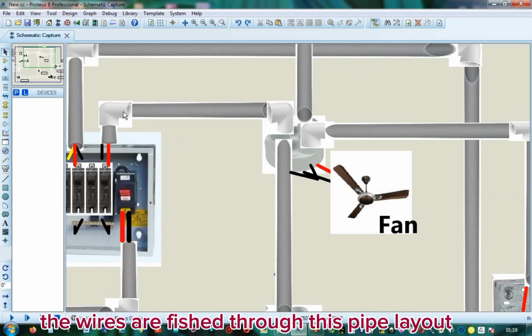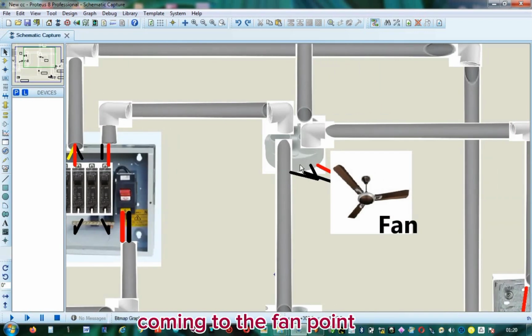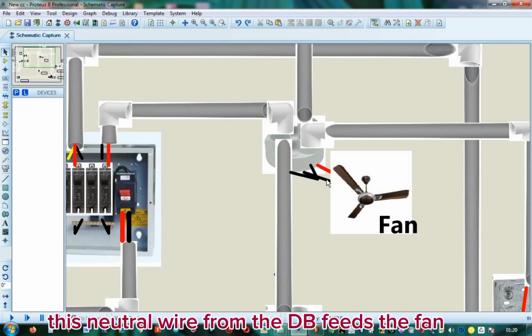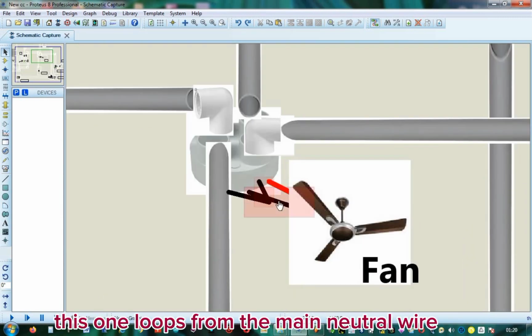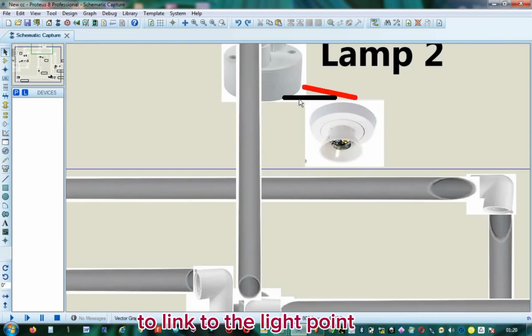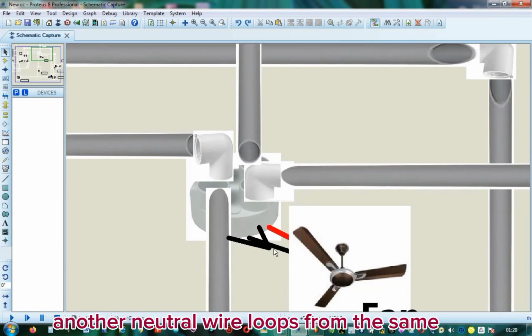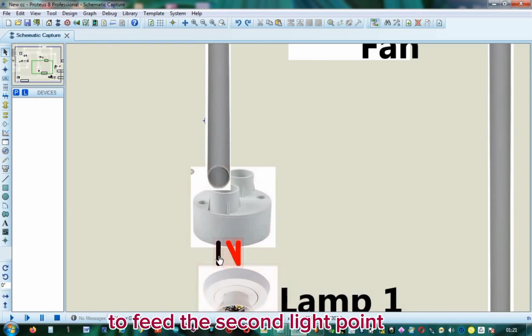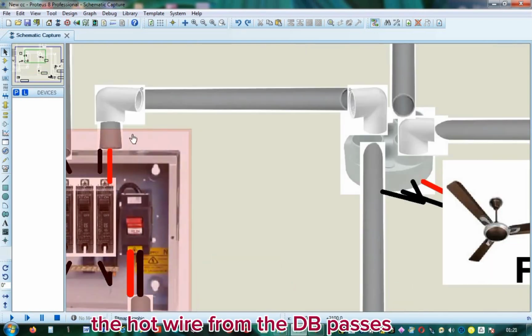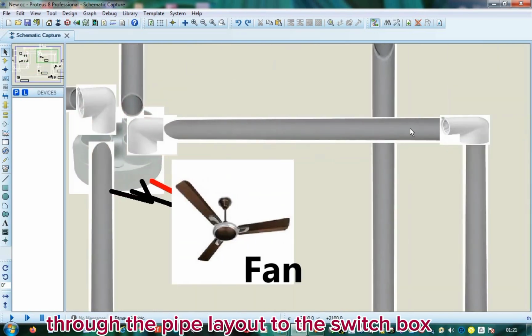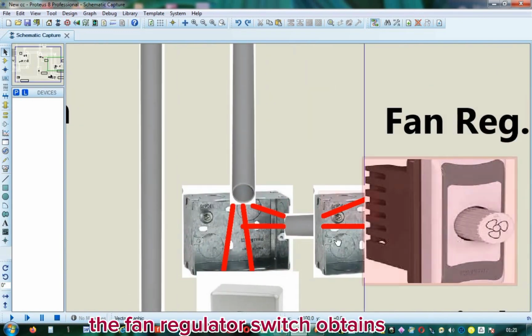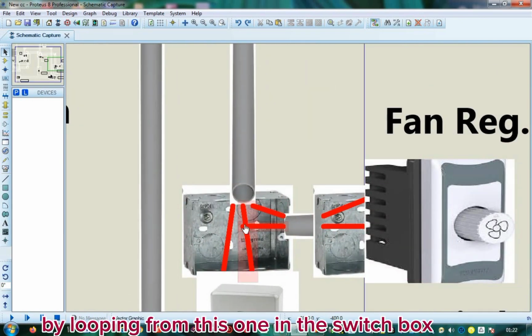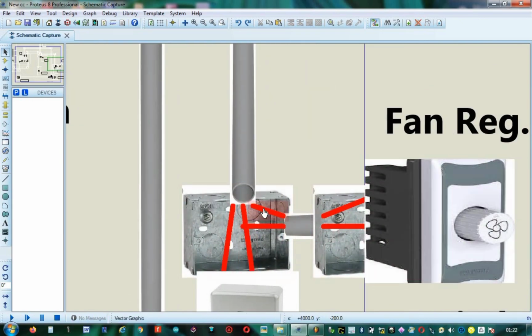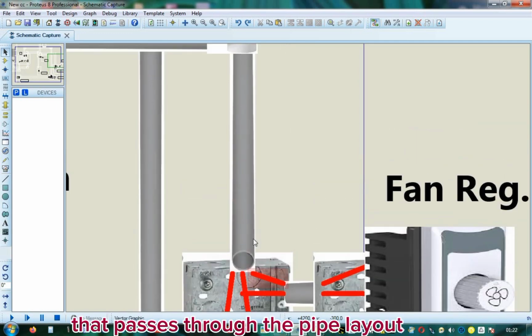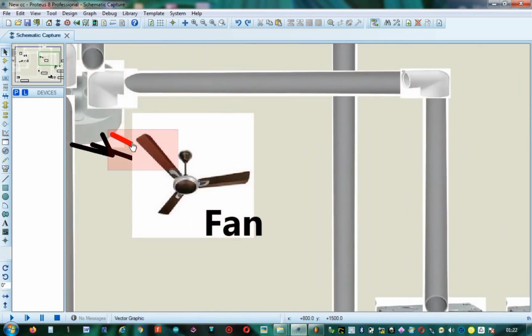The 2 wires are fished through this pipe layout, coming to the fan point where the neutral wire terminates. This neutral wire from the DB feeds the fan, then this one loops from the main neutral wire to link to the light point. Another neutral wire loops from the same main neutral wire to feed the second light point. The hot wire from the DB passes through the pipe layout to the switch box. The fan regulator switch obtains its hot wire by looping from this one in the switch box. This is the branch wire that passes through the pipe layout to supply power to the fan.